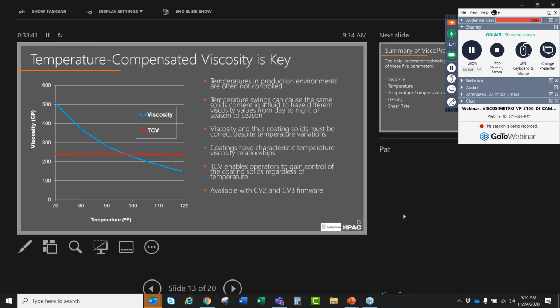And so TCV, or temperature compensated viscosity, which is based on an ASTM method, specifically method D341, defines how the fluid reacts to changes in temperatures, right? And we use a log-log equation to program this into the viscometer. And so this tells us what the viscosity would be at a fixed reference temperature. And we use that to control, right? So now if the temperature drops, the viscometer is not going to increase control and add more solvent to the process. It's going to be controlling on that temperature compensated viscosity number to ensure that it maintains the correct solids content of your ink or coating.